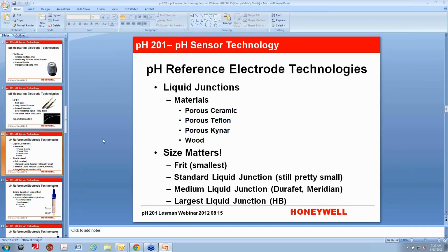So, and there's a variety. The most common I see out there is porous ceramic, and I think that's also the oldest material. The second most common is probably porous Teflon. I like the porous Teflon because the pores are a little bit smaller, and you can get them a little more irregular when you dope the Teflon and burn out the doping material. You just fire it out, and then you get all these holes in there. They're teeny tiny holes. You can't really see them. Porous Kynar, I haven't seen really good results with that. I've seen a few sensors with porous Kynar.